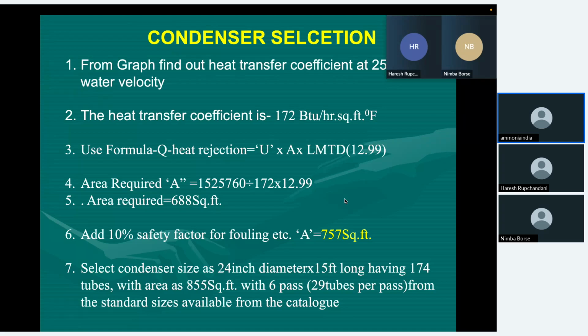Select a condenser size which is a standard size. You can't manufacture a new size every time. The manufacturers have standard sizes: 20-inch diameter, 24-inch diameter, 30-inch diameter. So we select the next size, 24-inch diameter, 15 feet long, 174 tubes with 855 square feet area and a 6 pass arrangement. So around 29 tubes per pass from the standard available catalog.